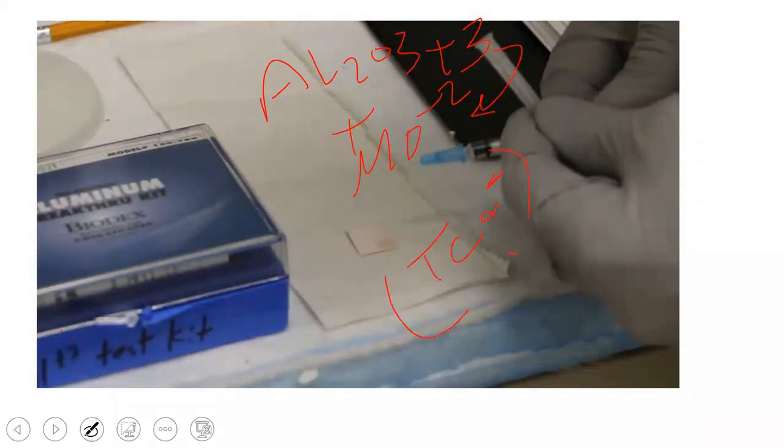This is the alumina breakthrough test. Look here, he is taking a drop and placing it on a strip. This drop contains alumina, which is Al2O3 that I mentioned earlier. The alumina is present inside the generator, and it is strongly linked to molybdenum. There is a very strong binding between the two. Technetium has a negative charge, and the binding energy of technetium with alumina is less than the binding energy of molybdenum with alumina. Is that clear?